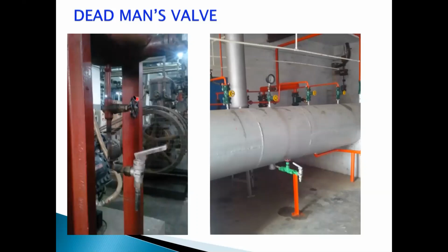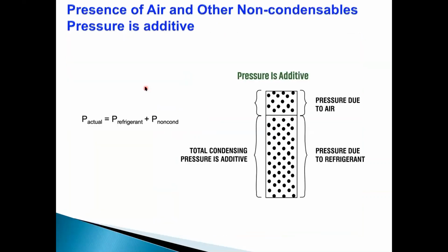When you want to drain, you open this valve, operate the handle, and oil will drain. Once the handle is released, the valve closes automatically. Once your drainage is complete, you close the valve, and operate the handle again, so anything trapped will be released and the draining is complete. This is a very, very important valve, because normally this valve is a multi-turn valve, and it takes around 14 to 18 turns, depending on the manufacturer. So when the valve is open and ammonia starts leaking, it becomes very difficult for the operator to close. So these are all safety devices.